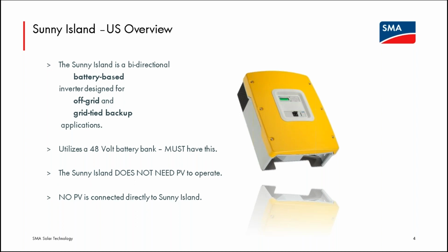Generally, the benefit of that is that a homeowner gets to use their normal AC appliances in an outage situation. They don't have to worry about DC appliances that may be more efficient, but generally costly and not as readily available. So SMA is definitely an advocate of AC coupling. While someone can use PV and couple it via a charge controller onto the DC side of the Sunny Island, no PV modules will ever wire directly to the Sunny Island.